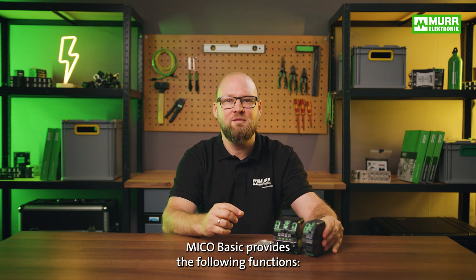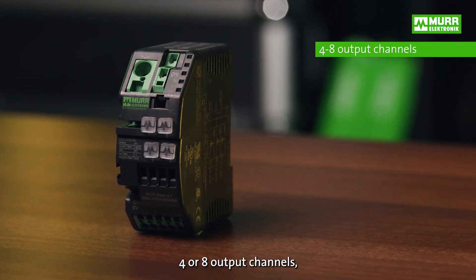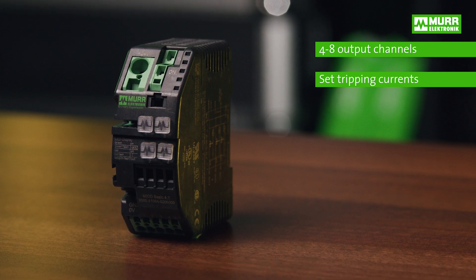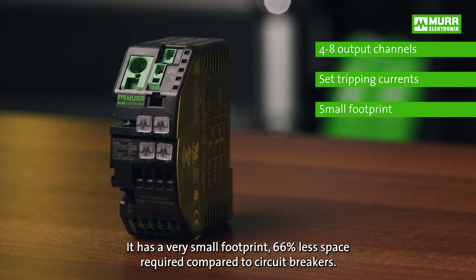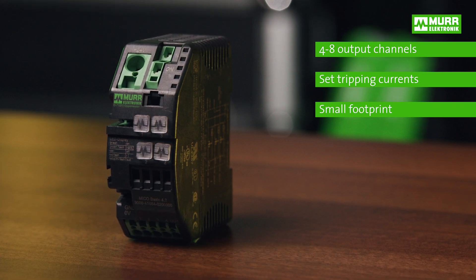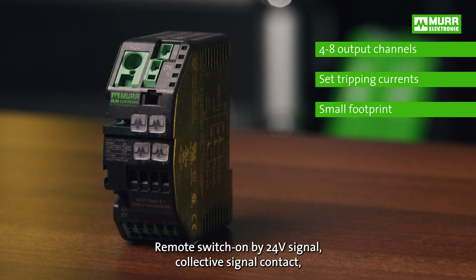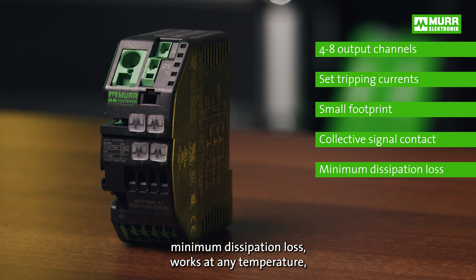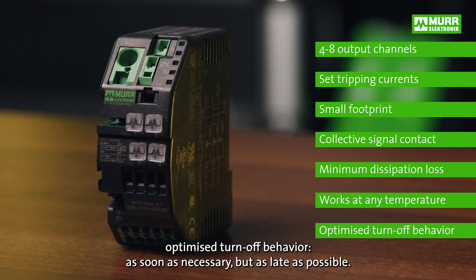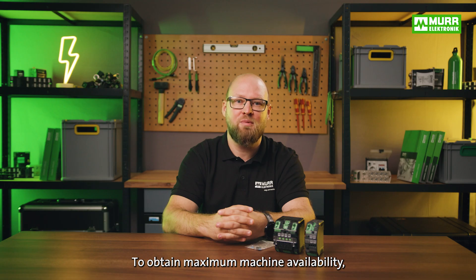MICO Basic provides the following functions: four or eight output channels, set tripping current to four or six amps. It has a very small footprint — 66% less space required compared to circuit breakers — remote switch on by 24V signal, collective signal contact, minimum dissipation loss, works at any temperature, and optimized turn-off behavior as soon as necessary but as late as possible.